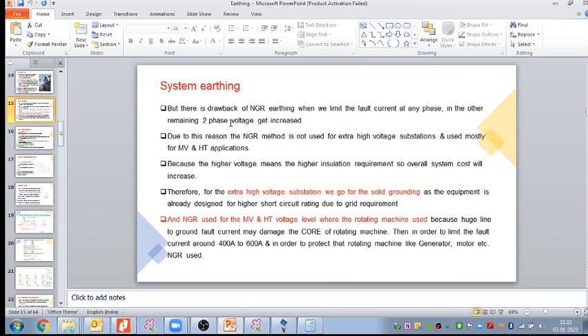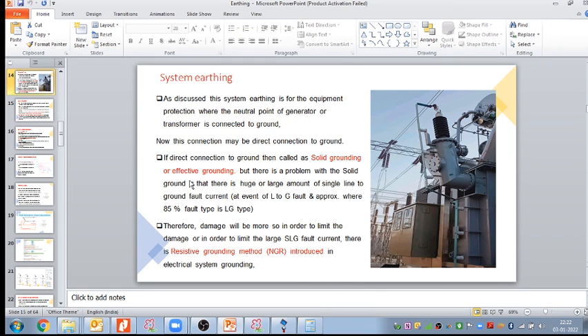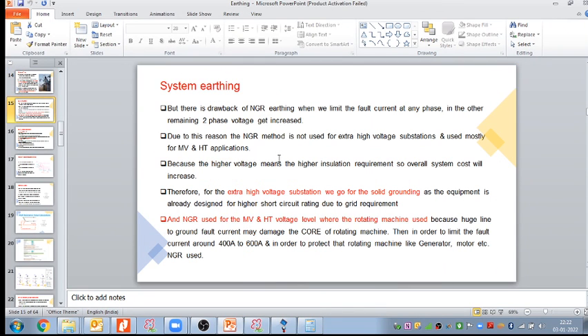But there is a drawback of NGR. Yes, NGR can limit the fault current, but again there is a drawback. When we limit the fault current at any phase, the voltage in the other remaining two phases gets increased. Due to this reason, the NGR method is not used for extra high voltage substations and is used mostly for medium voltage and high voltage or HT applications.